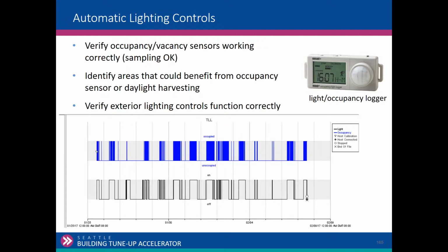So obviously if you're doing your walk down and the outdoor lights are on, that's it. Well, I've got to figure out, is it a photocell? Is it a time clock? Is it a photocell that's working correctly? Is it a time clock that's not programmed? That's a deficiency that needs to be fixed. That's a low cost, no cost efficiency.